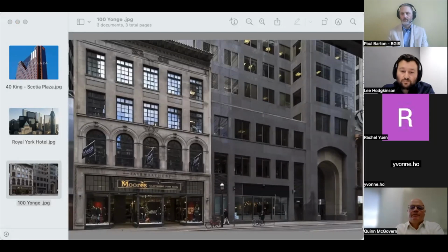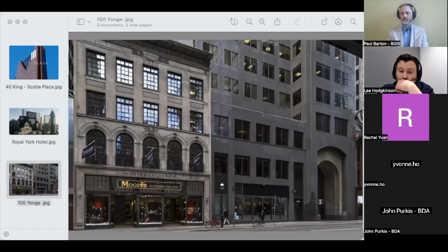We've never had to run it over 160, and this one's been up and running since last November. So we had one design day of -20 last February, and we ran the building at -20. We actually turned everything on. It happened on a Friday, and as you may know, in Toronto, not everybody comes to work on Fridays these days. So we did turn on all the ventilation systems and made sure we tested the system outright, and it passed.